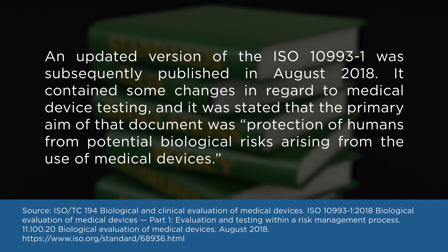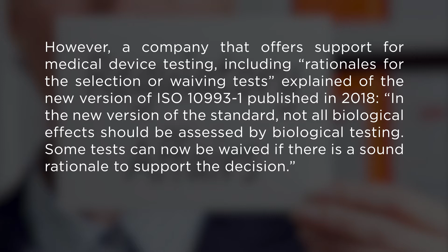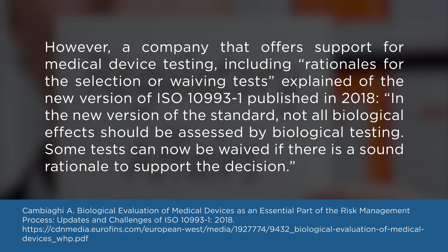However, a company that offers support for medical device testing, including, quote, rationales for the selection or waiving tests, end quote, explained of the new version ISO 10993-1 published in 2018, quote, in the new version of the standard, not all biological effects should be assessed by biological testing. Some tests can now be waived if there is sound rationale to support the decision, end quote. The source for this is Biological Evaluation of Medical Devices as an Essential Part of the Risk Management Process, Updates, ISO 10993-1, 2018.